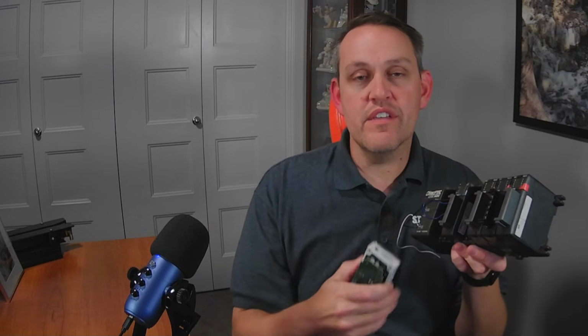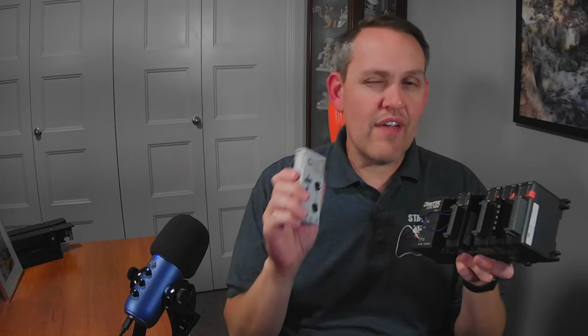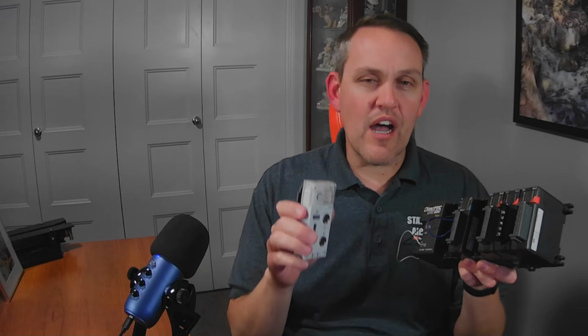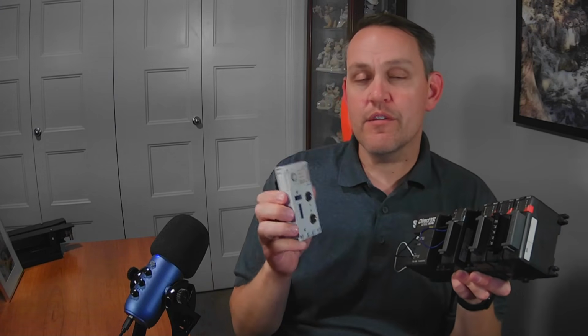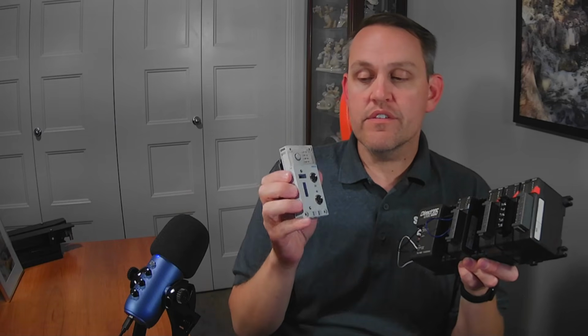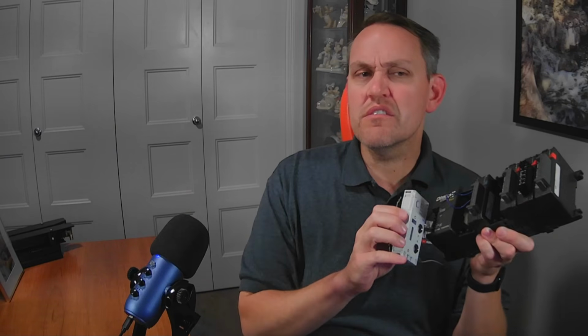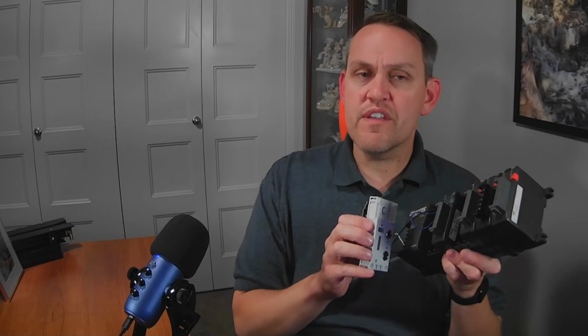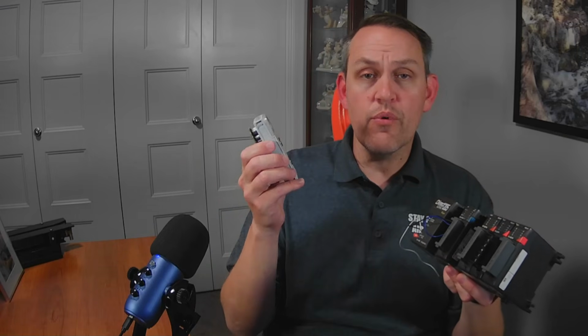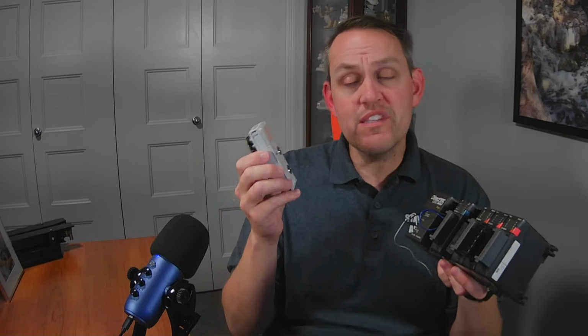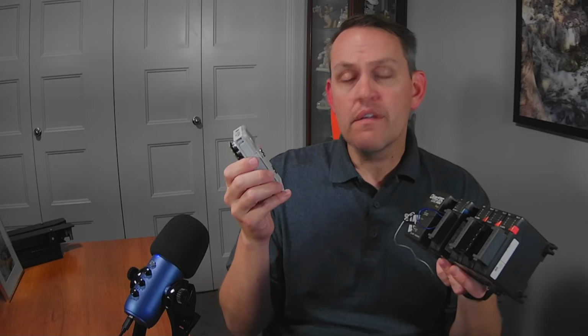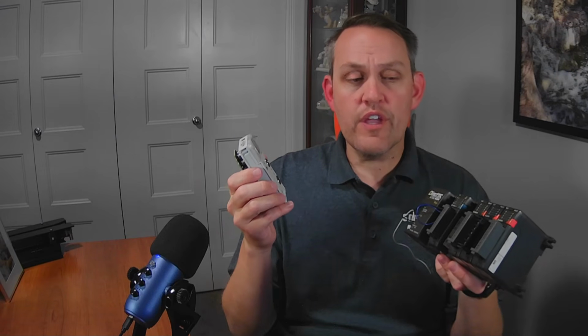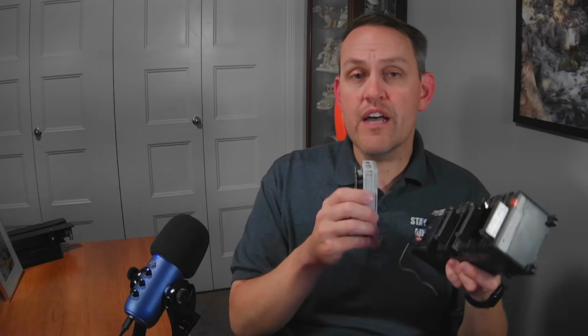The main PLC might have 200 points coming in and out of it. The safety PLC is just going to have a handful of critical points, e-stops, brake monitoring, some things like that, block control. And the safety PLC is basically just double checking everything it does. So the main PLC says, I'm going to let this train go, and the safety PLC and its program, running a completely separate program inside of it, has to agree, yeah, I'm good with you letting that train go, and then the main processor is allowed to let the train go.